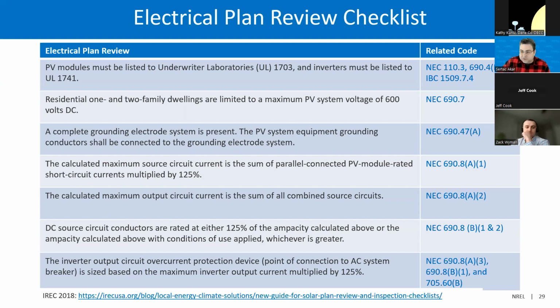And this is another important thing. The calculated maximum source circuit current must be the sum of the parallel-connected PV module rated short circuit currents multiplied by the 125% value. And the calculated maximum output circuit current must be the sum of all combined source circuits. DC source circuit conductors are rated at 125% of the ampacity calculated above, with conditions of use applied, whichever is greater. And finally, the inverter output circuit overcurrent protection device, at the point of connection to the AC system breaker, is sized based off the maximum inverter output multiplied by its 125% value.